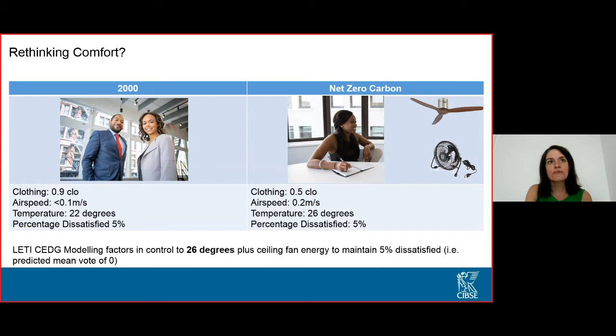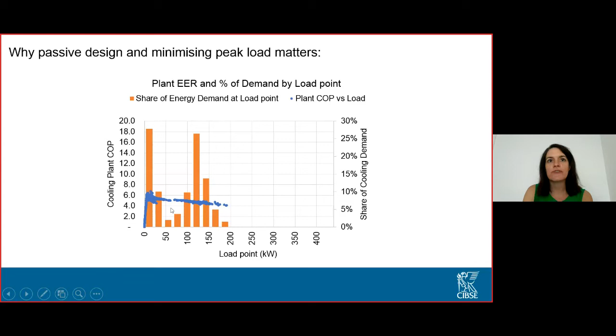And the reason that this matters is this chart here shows, within the blue section, the cooling plant energy efficiency ratio, or EER, for each hour of the year within the simulation. And what we've done by being able to minimise our overall plant capacity is ensure that our plant is still operating efficiently at low load and throughout the hotter seasons of the year where we are seeing this peak cooling demand. Through the middle here is where we've introduced external openings, operable windows, to really keep that peak load down during the mid-season.